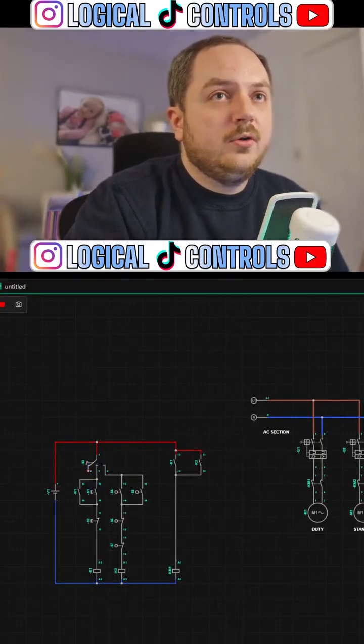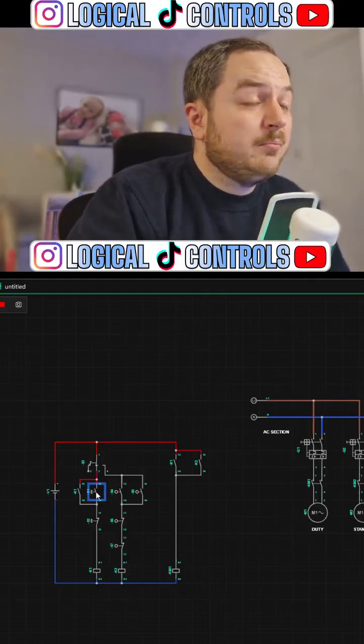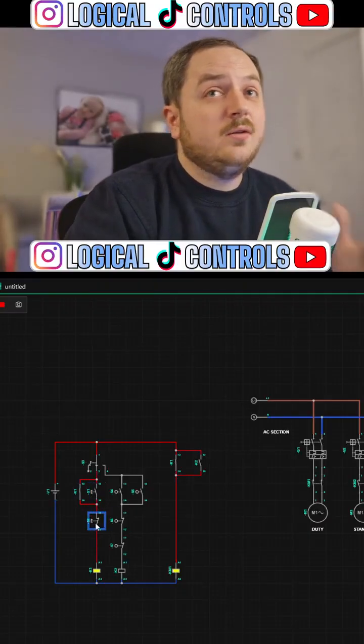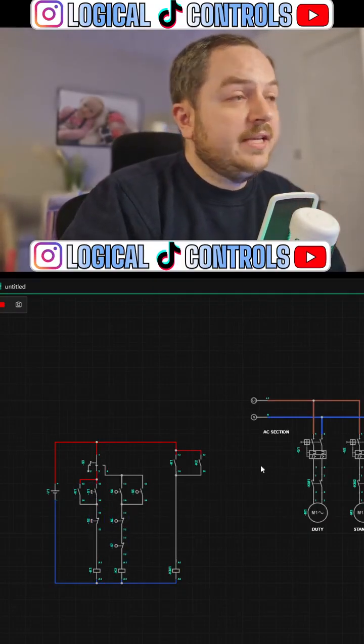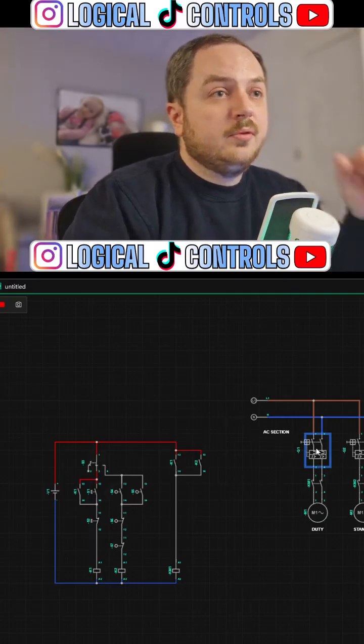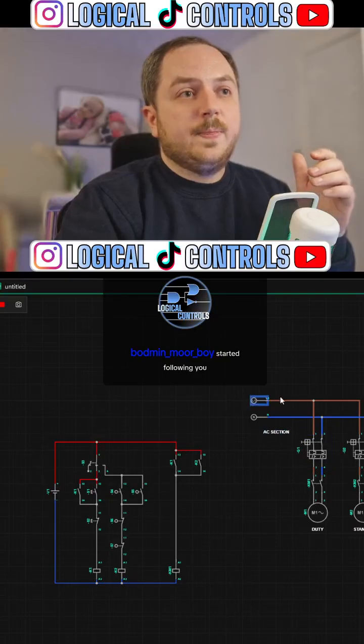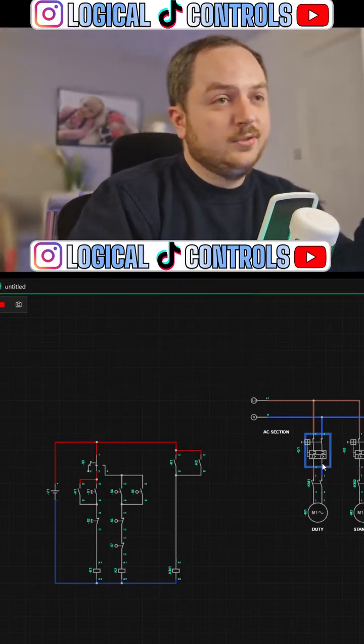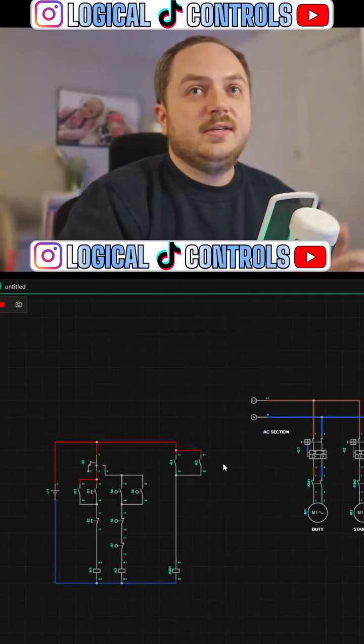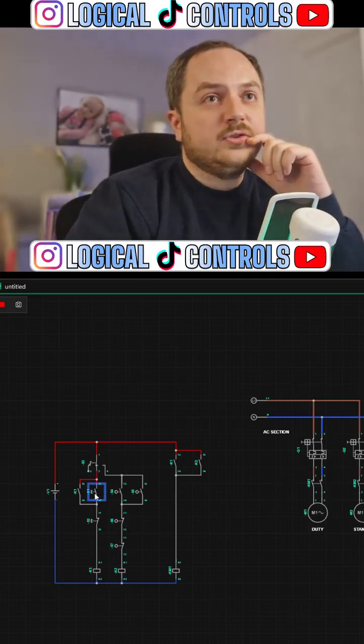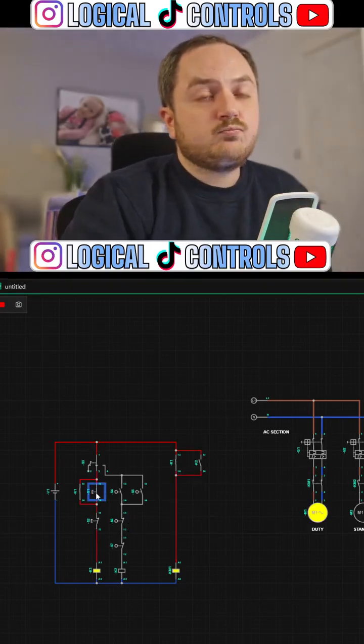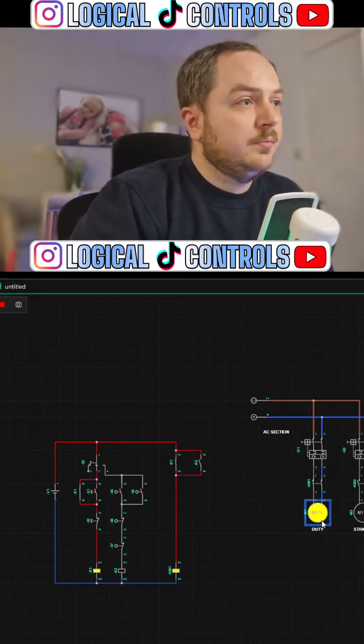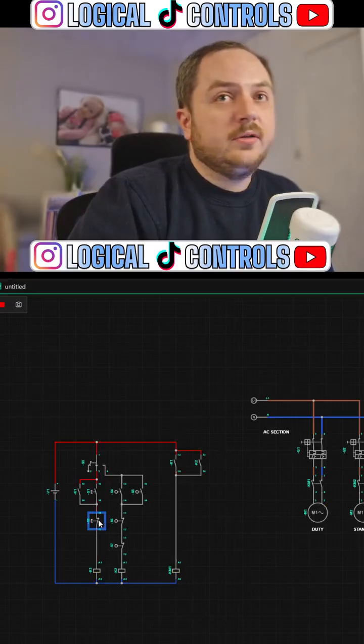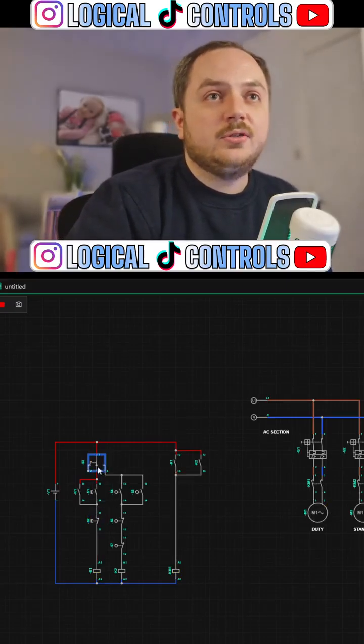So we're in off mode. I'll switch it into manual mode. I press the start button - we should get a start. We don't, because I'm an idiot and I didn't close up the motor starter circuit breakers over here, so on the AC side you need to close up the protection, of course. Right, okay, we'll try again. Press the start button, the pump comes on. Press the stop button, the pump goes off. Right, good, manual works okay.